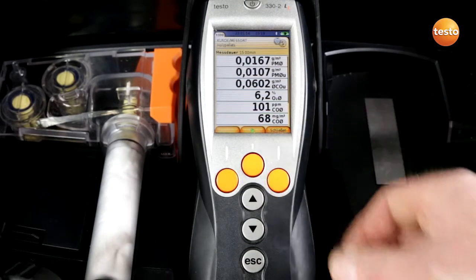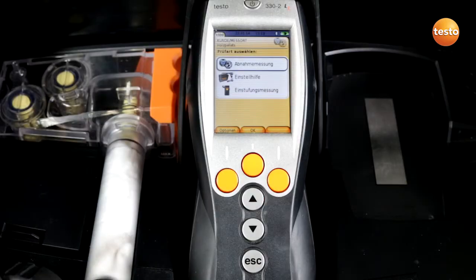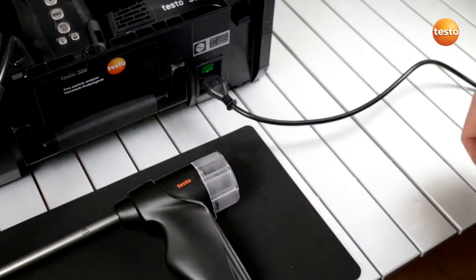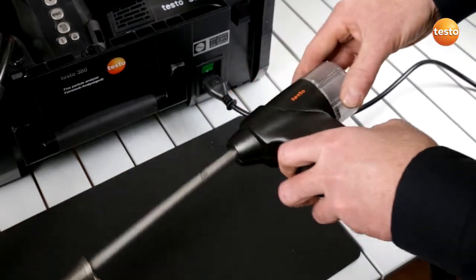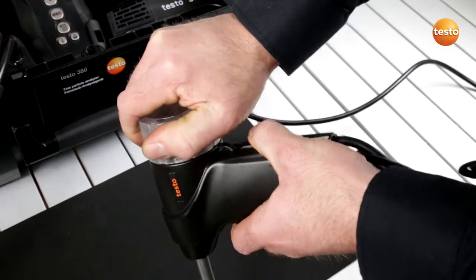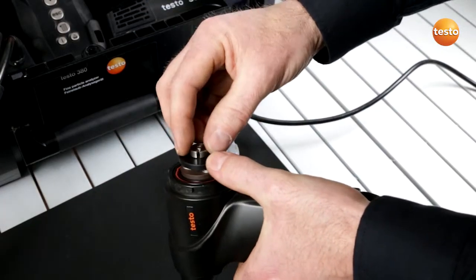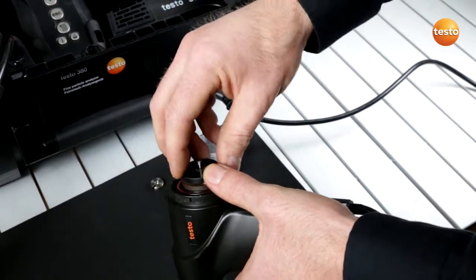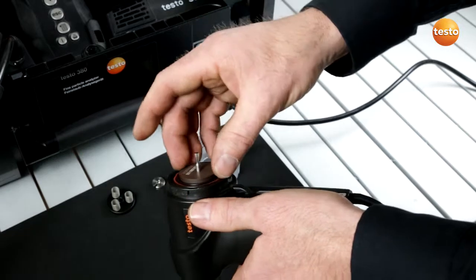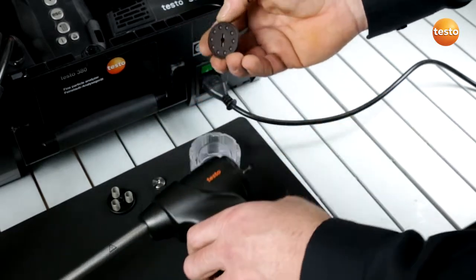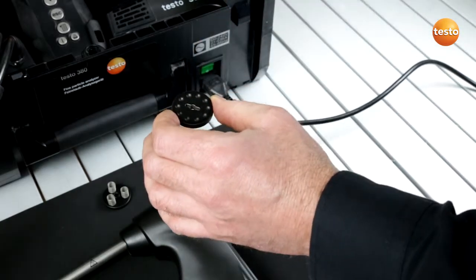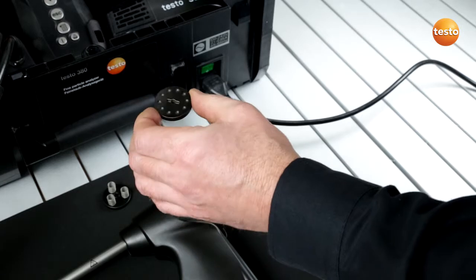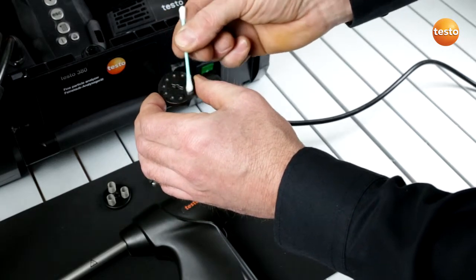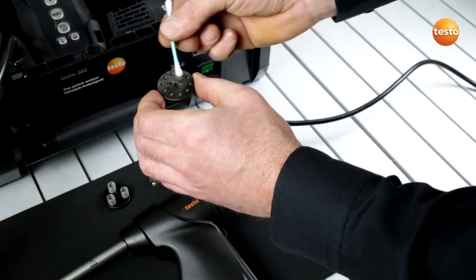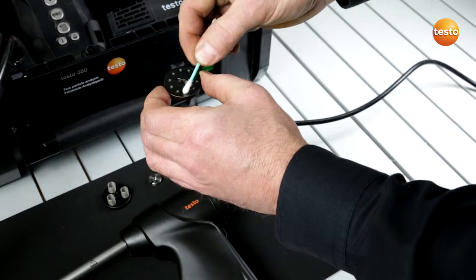I close and the data are saved. I can now decide whether I want to carry out a further acceptance inspection or start with the cleaning of the instrument. I begin with the cleaning of the rotation diluter. To do this, I open the cover at the rear, release the locking mechanism, and remove the rotation disc. I clean the rotation disc with a Q-tip which is moistened with distilled water. I then dry it with the dry end.